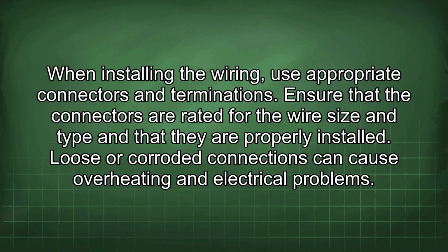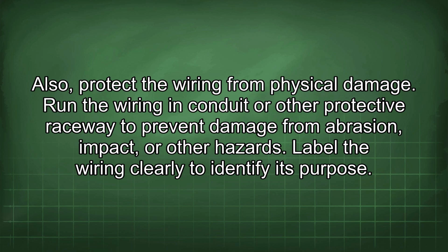When installing the wiring, use appropriate connectors and terminations. Ensure that the connectors are rated for the wire size and type and that they are properly installed. Loose or corroded connections can cause overheating and electrical problems. Also, protect the wiring from physical damage. Run the wiring in conduit or other protective raceway to prevent damage from abrasion, impact, or other hazards.